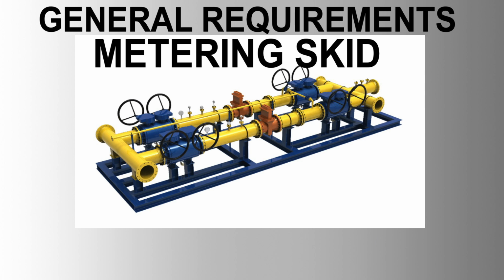and reliability. Vendor requirements. Vendors must provide all necessary certifications to support specified test requirements such as seismic, chemical, and physical testing. Vendors should have a QA/QC program in place and should be ISO 9000 certified. Calibration must be performed individually on each instrument with appropriate tags indicating readiness for installation. Vendors should supply frequency and stress analysis calculations for thermowells, demonstrating suitability for specific line velocities and conditions.